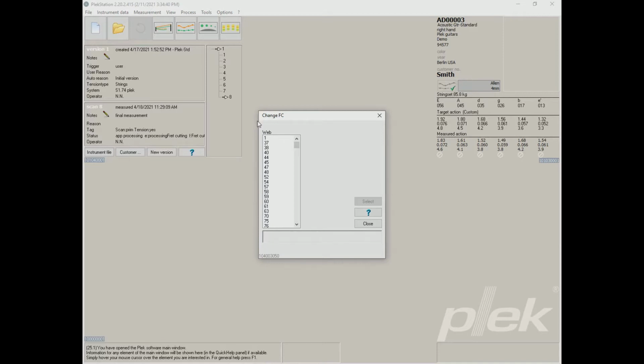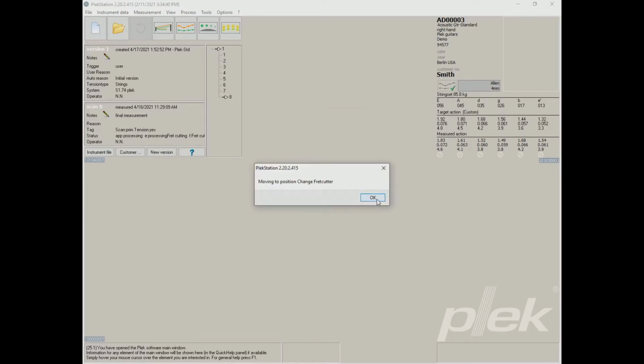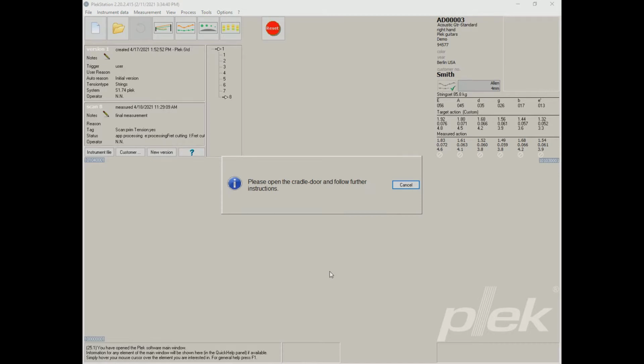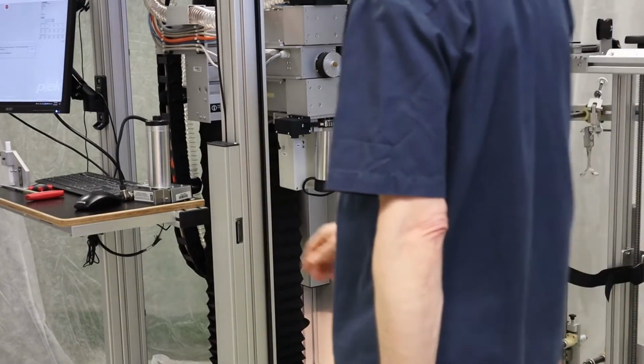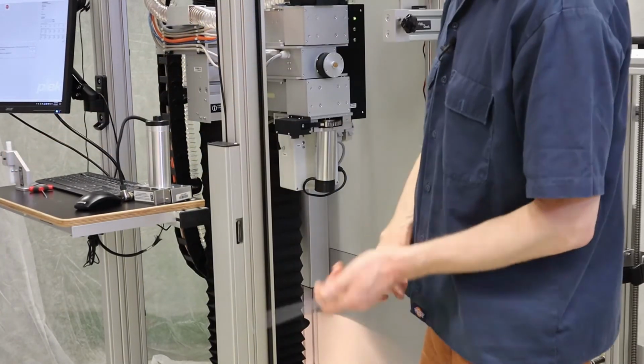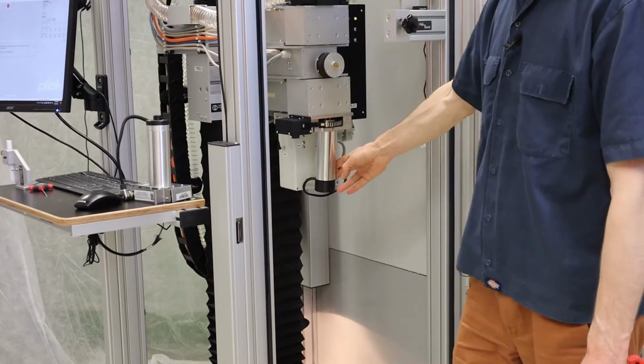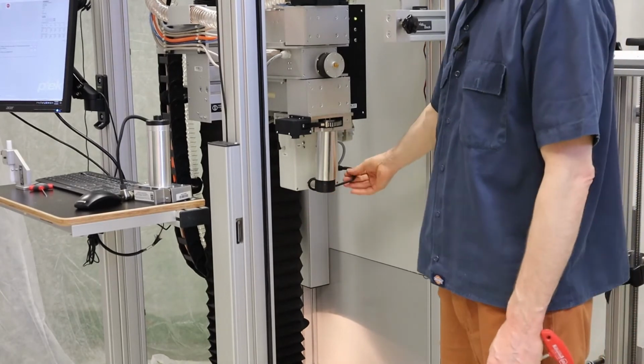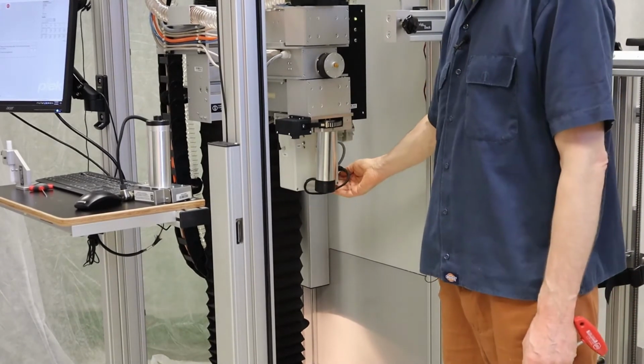So we have FC 128. We find that in the list, and I'll select that. So you select, I am sure, yes, and I click OK. Now the machine moves to the position where you can open the door and access the machine. So the first thing I want to do is remove the old cutter. There's a cable that comes out of the motor on the bottom, and it's plugged into this controller box in the back on the side.